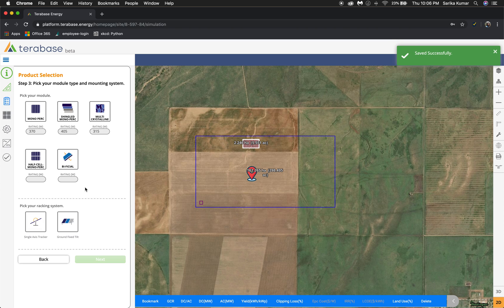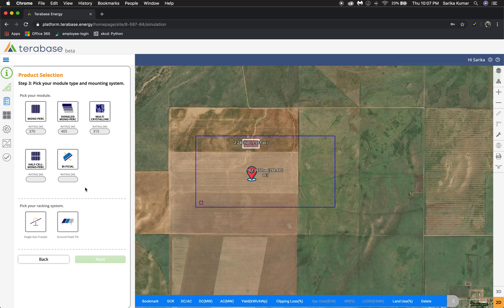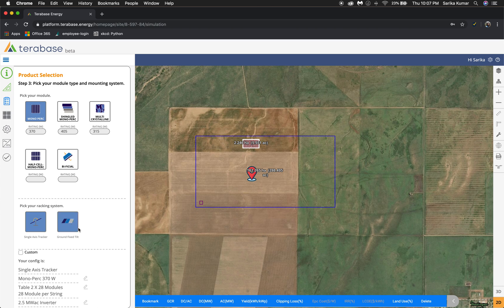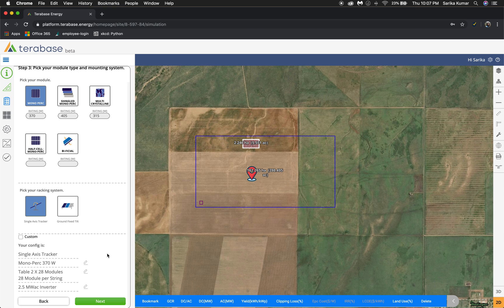In this step you're going to pick your module and your mounting system. I'm going to go with a mono PERC and a single axis tracker, and then conveniently it automatically assigns an inverter. For this setting it's given us a 2.5 megawatt inverter and 28 modules per string. Then I'm just going to go ahead and click next.